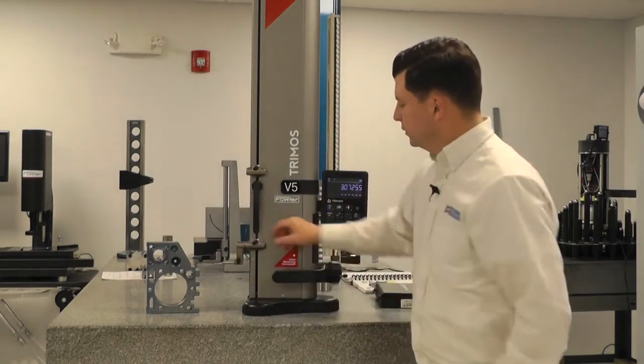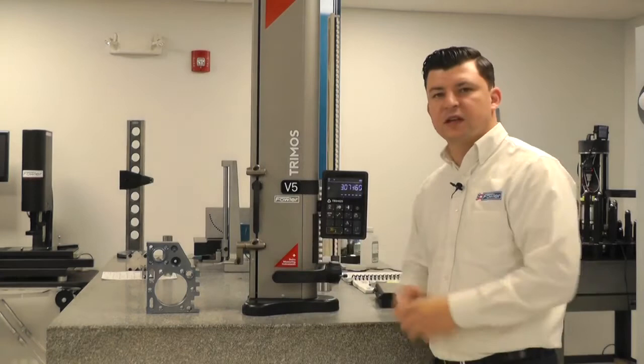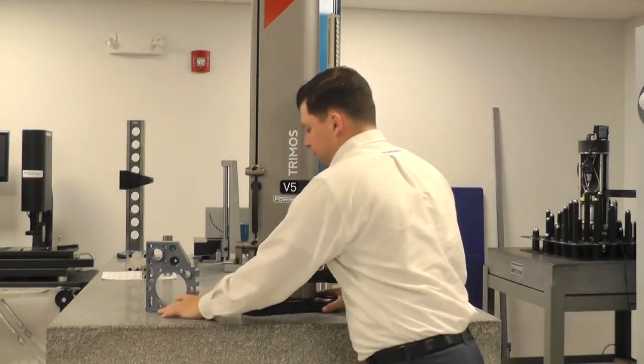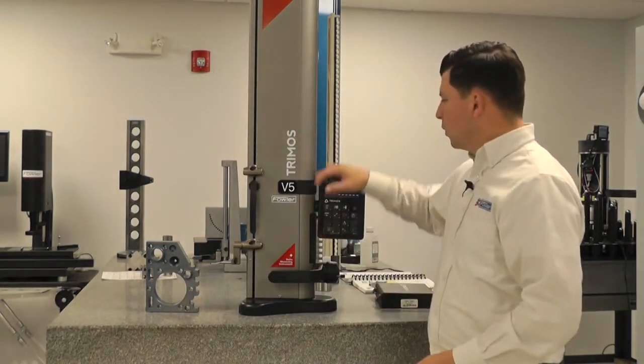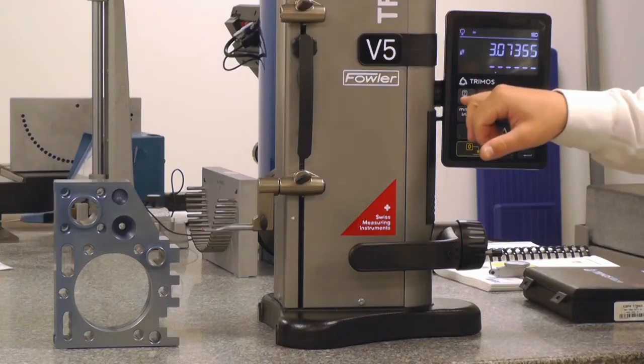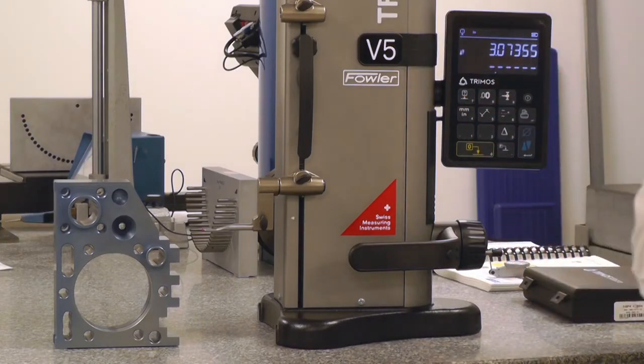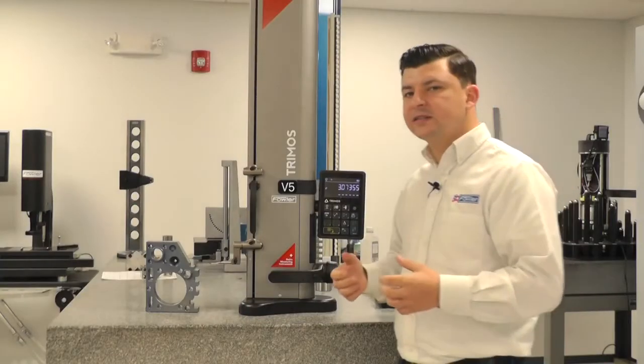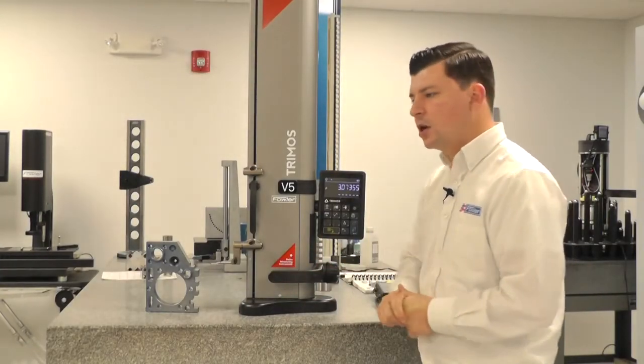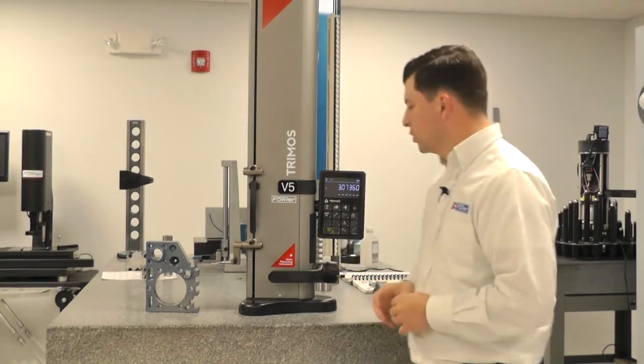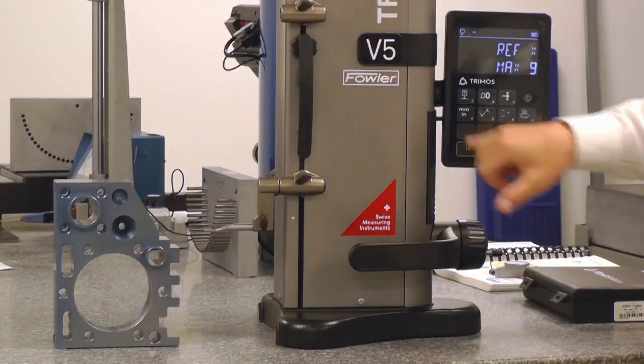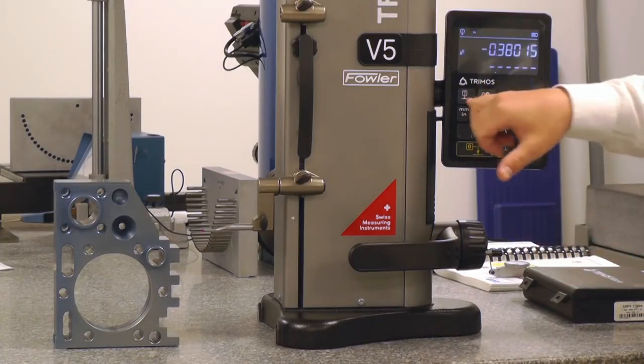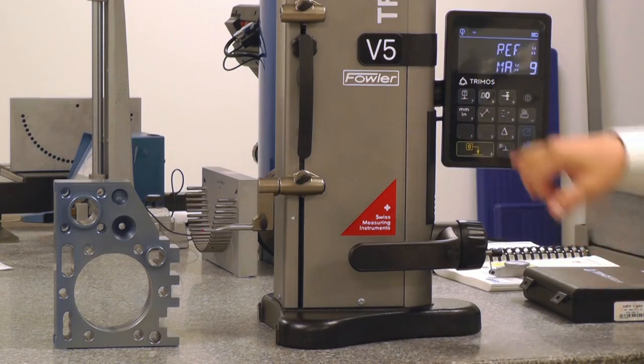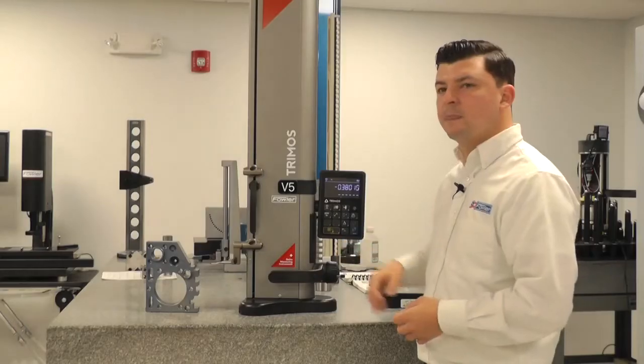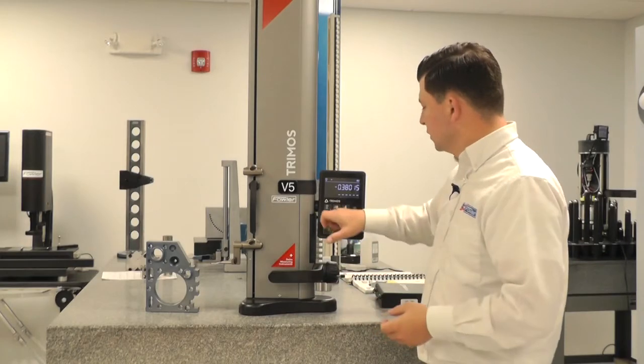So I will release my secondary carriage as we go to take some measurements. I will direct your attention to the display, as now number 7 is our reference feature. This is how we're going to establish different references. We can establish up to 9 references with this gauge. You might find multiple datums on your part, and we can establish those values. So if I say reference 1, reference 2, reference 3, so forth all the way out to reference 9, we can establish up to 9 references.